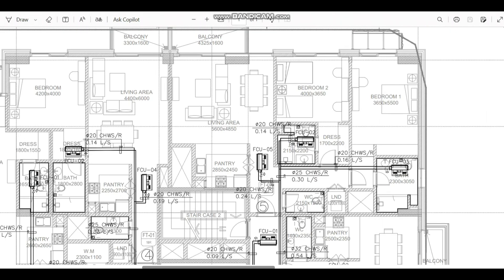Here you can see the chilled water or district cooling connection. The pipeline is coming and connected — the supply line is connected to the left side of one unit. Coming to the other unit, the supply side is connected to the right side. So when it comes to material ordering, we normally consider only the FCU capacity — ton of refrigeration, air flow, coil temperature — and we order the material. But what I particularly do, especially for a project with 700 or 800 FCUs, I check whether the chilled water connection is needed on the left side or right side of the FCU.